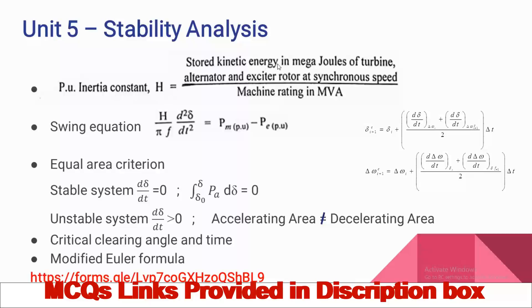The important formula is the per unit inertia constant H, which equals stored kinetic energy of the turbine-alternator and exciter rotor at synchronous speed in mega joules, divided by machine rating in mega volt amperes. The swing equation is: (H divided by π·f) multiplied by (d²δ/dt²) equals Pm per unit minus Pe per unit (mechanical power minus electrical power). By using the equal area criterion, we can determine system stability. If the system is stable, dδ/dt equals zero.